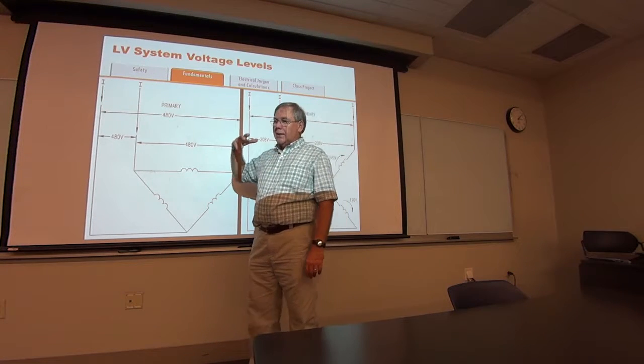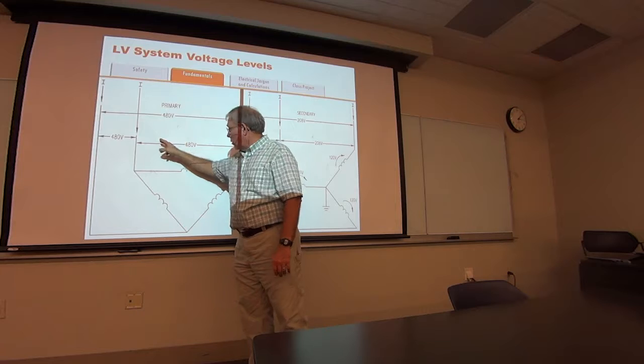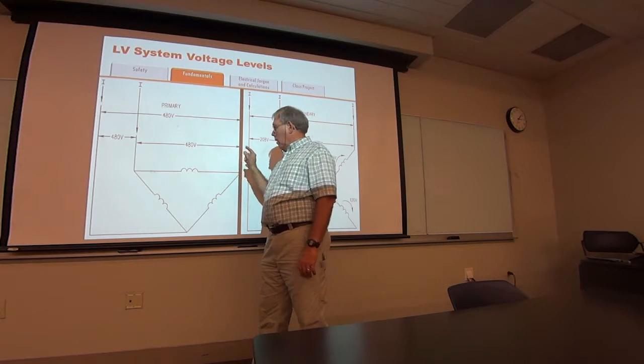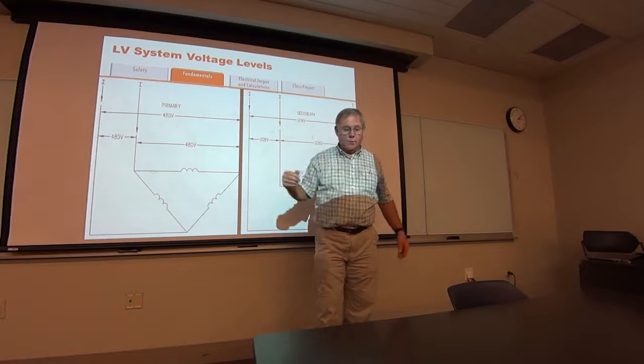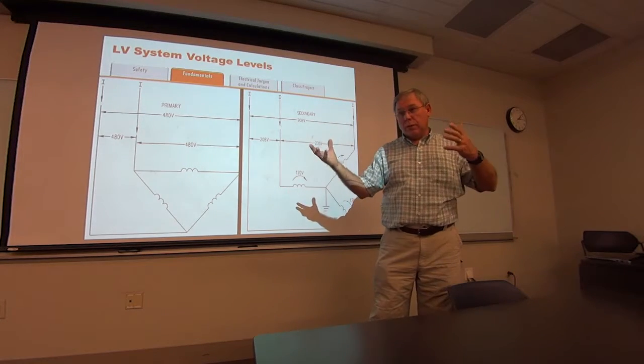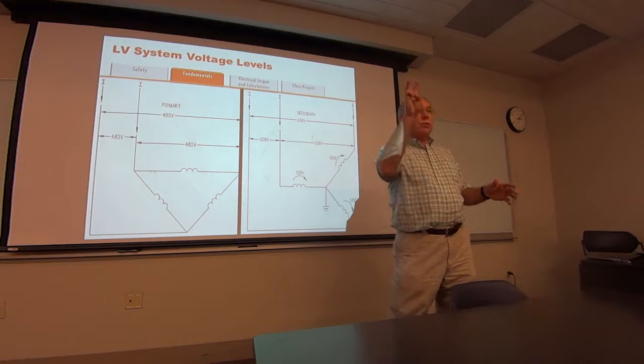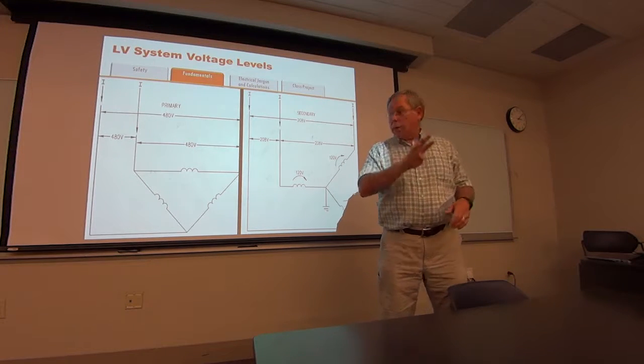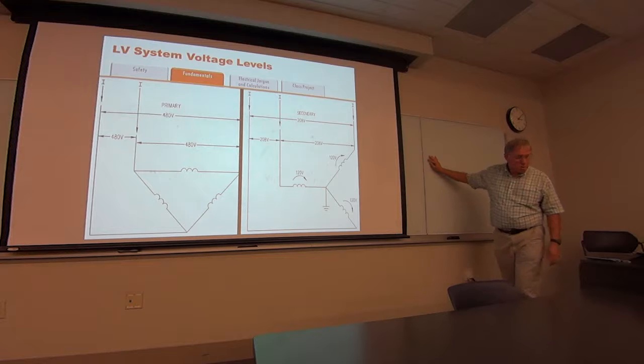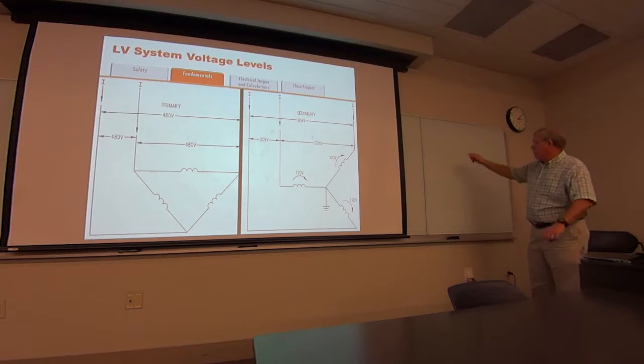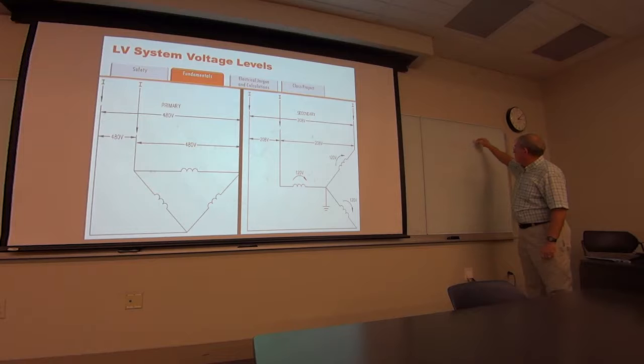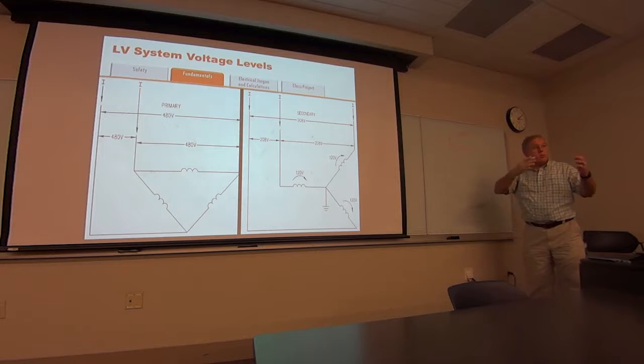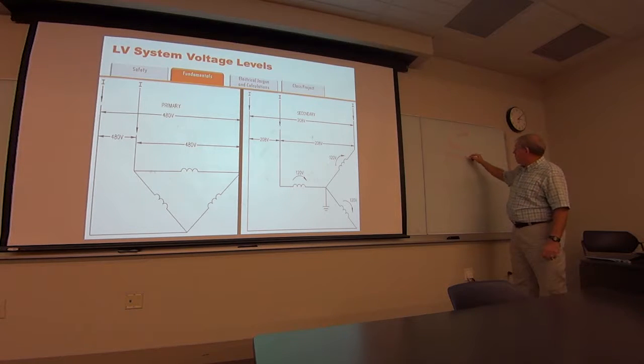On a 240 volt delta three-phase circuit, that's 240 volts across it, right? Now, at your house, that right there, well, that's 208 probably, because everything in the building is three-phase. But at your house, if you go out and look at the transformer, it's got 3 little lugs on it. And that transformer has... can I write on this? You can. There's a pin there. Okay. You've got a transformer coil up here, and this is probably 12470 volts. That's the utility. Then you've got a secondary on that transformer. And this is 120 volts here and 120 volts here.